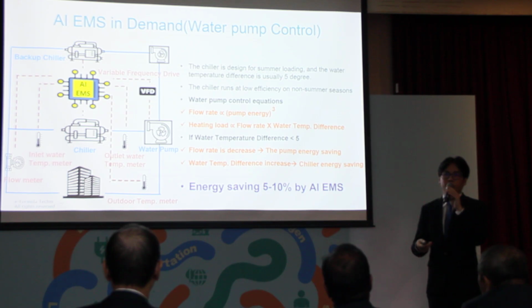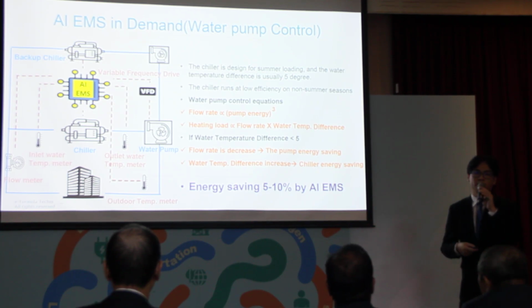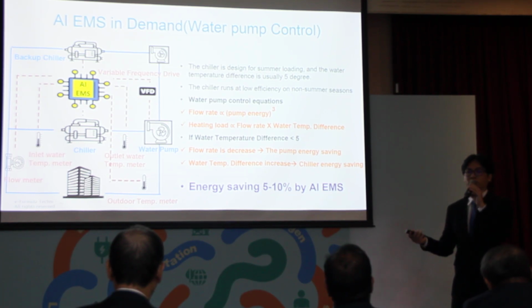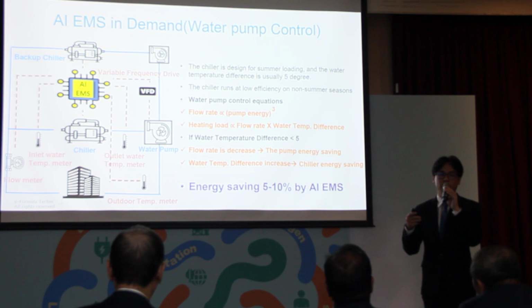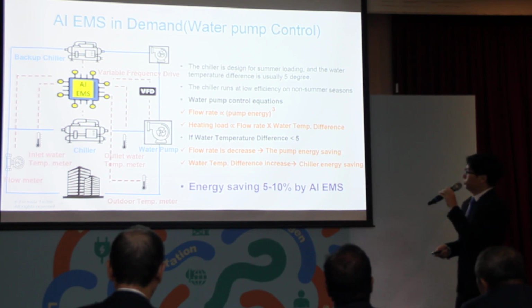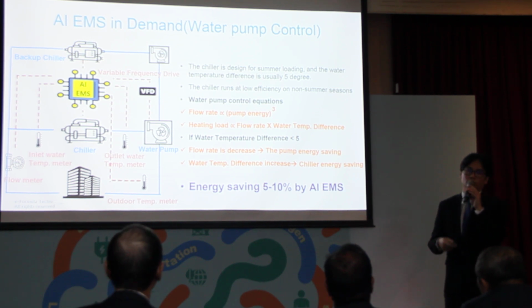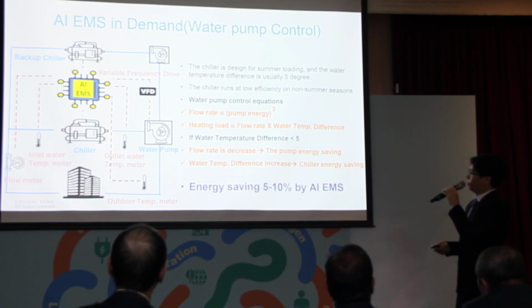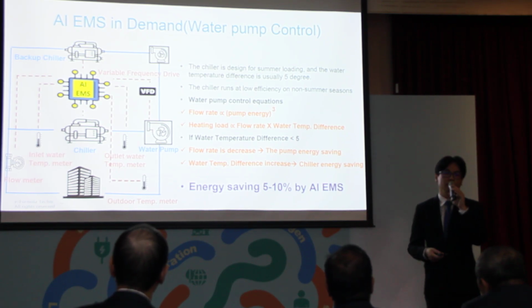At the same time, from equation 2, if we reduce the pumping flow rate, the water temperature difference is increased. So it also means that the chiller system will operate from low loading to high loading, so it can enhance the chiller system's efficiency.